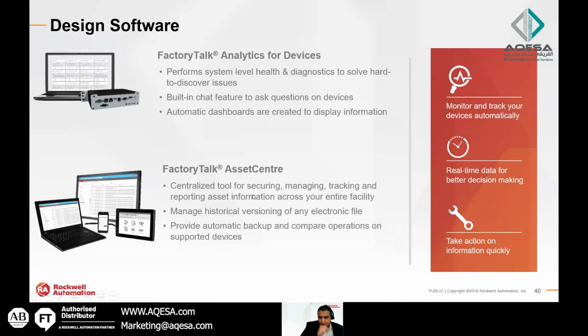Back to Asset Center. It is software that you install on a server. It will monitor all the CPUs, VFDs, HMIs, and software like FactoryTalk View, and it will make a backup, whatever interval you choose, every day, week, or month, and compare the backup with the physical one. At a lot of sites, the maintenance engineer will go solve a problem, make a software jumper, change a timer, change something, and leave the site without recording it. FactoryTalk Asset Center will prevent that.